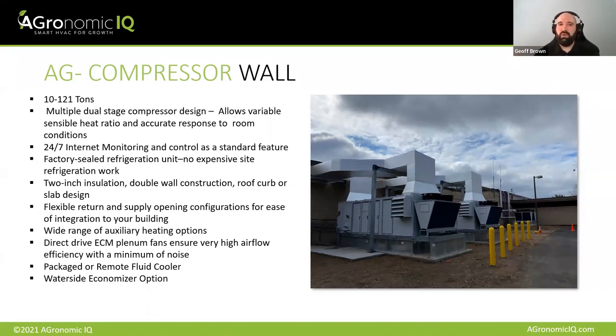So we're able to turn those compressor circuits on or off and at different stages, again, to very tightly tailor the work that we're applying to the room demands, the stage of your plants. If you're in veg phase, whether those plants are small, and following them through the flower cycle, through sort of week 6 of flower, where your dehumidification demand is absolute peak, and then back again as that flower cycle ends, you start cooling things off, drying things down.